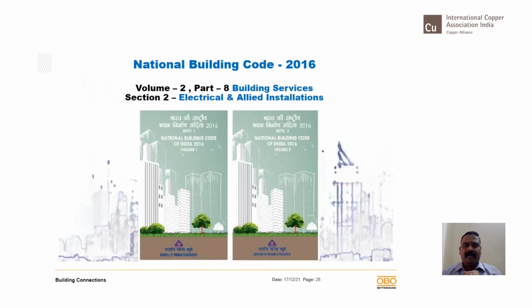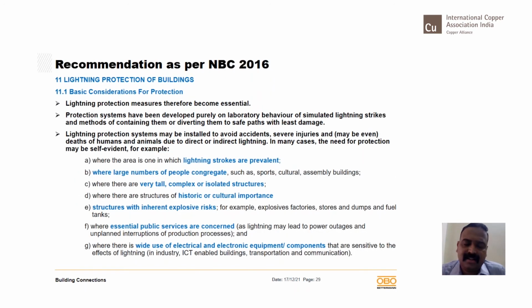Now, National Building Code 2016, Volume 2, Part 8, Section 2, Electrical and Allied Installation talks about this in detail, which is covered in the IS-IEC standard also. So I'll just rush through what is said here. Basic considerations for protection under 11.1. Lightning protection may be installed to avoid accidents, severe injuries and death of humans and animals due to direct or indirect lightning. In many cases, the need may be self-evident. For example, where the area is one in which lightning strokes are prevalent, where a large number of people congregate, such as sports, cultural and assembly buildings, where there are very tall, complex or isolated structures, where there are structures of historic or cultural importance, structures with inherent explosive risk, where essential public services are concerned, where there is wide use of electrical and electronic equipment.